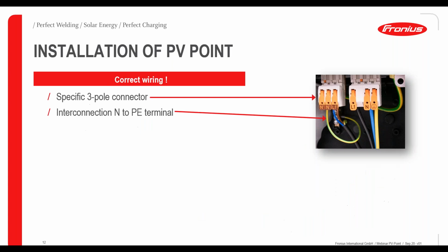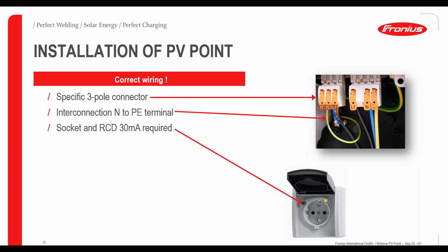If we go into the pictures to see how it's done, you see here the specific 3-pole connector. This is in the inverter, just beside the AC connection. So when you have a Symo, you would have a 3-phase connection here, of course. In this case, it's a Primo, which will be launched later, beginning of next year. There is an interconnection between neutral and the ground terminal, and then you go from that to the output to the socket. On the socket, you have different options. There's also one with an integrated RCD, which is maybe quite expensive. There is, of course, another possibility to just connect the RCD in an extra box right after the inverter, and then you go to the socket.